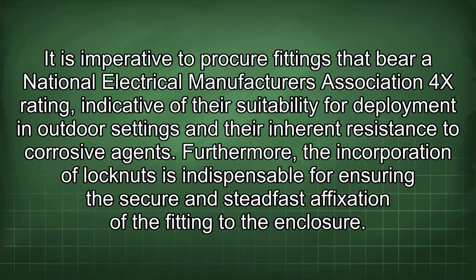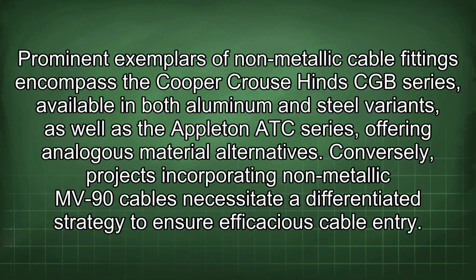Furthermore, the incorporation of lock nuts is indispensable for ensuring the secure and steadfast fixation of the fitting to the enclosure. Prominent exemplars of non-metallic cable fittings encompass the Cooper Crouse-Hinds CGB series, available in both aluminum and steel variants, as well as the Appleton ATC series, offering analogous material alternatives. Conversely, projects incorporating non-metallic MV-90 cables necessitate a differentiated strategy to ensure efficacious cable entry.